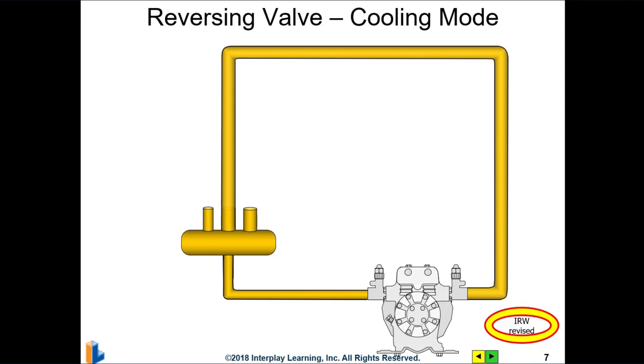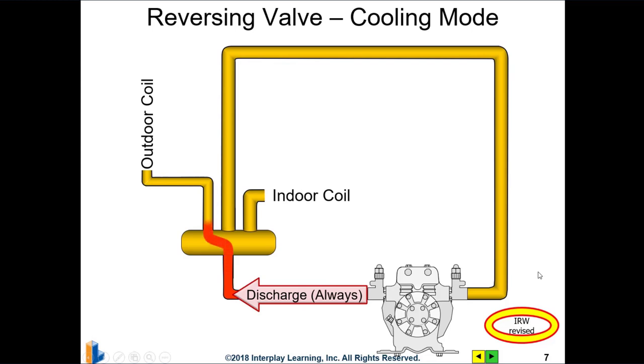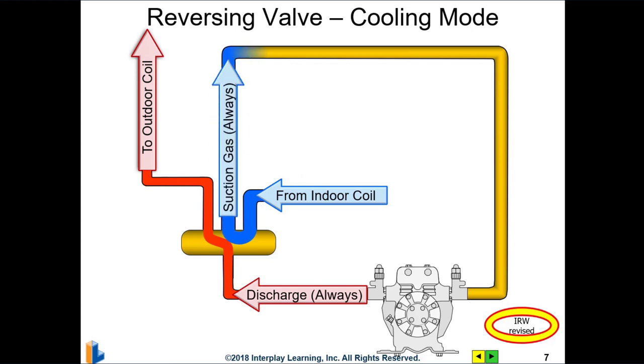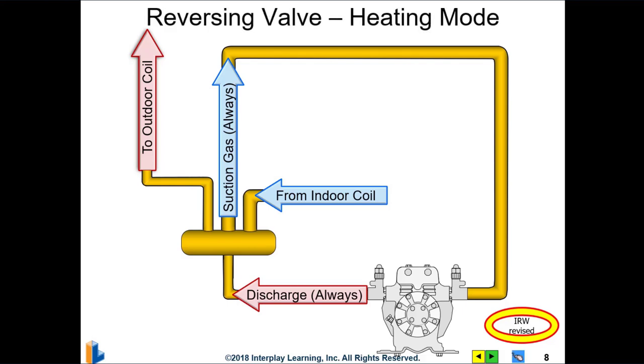The reversing valve in cooling mode takes the discharge gas through the permanent discharge port and sends it to the outdoor coil where it de-superheats, condenses, and sub-cools. The suction gas comes in from the indoor coil and goes back to the compressor. The valve may be energized into cooling mode or energized into heating mode — it depends on geographical location. In the northeast and other colder climates, some heat pumps have the four-way reversing valve that fails to the heat mode. In warmer climates like the south, many valves in those heat pumps are de-energized or fail to the cooling mode, meaning they have to energize the valve to get it to go to heating.